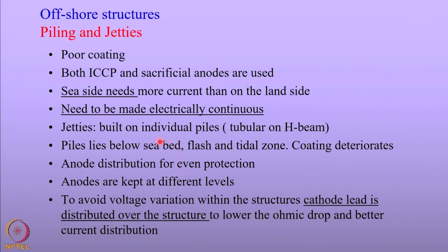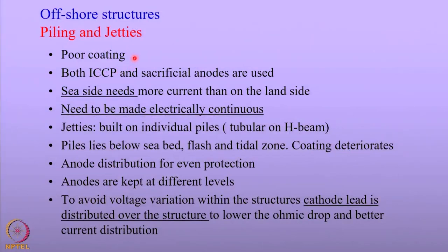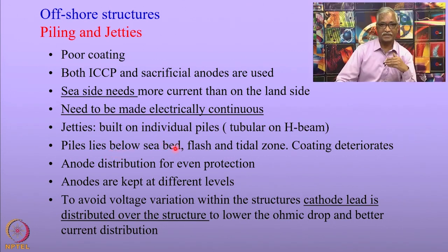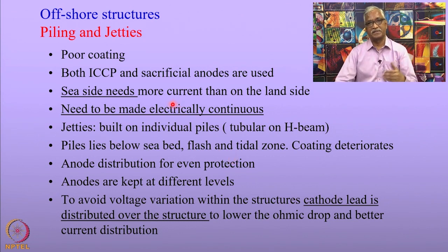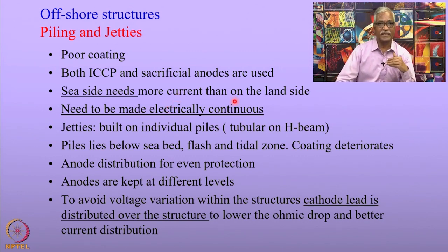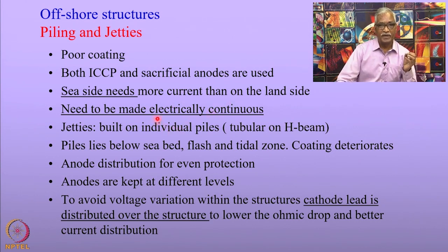Care needs to be taken to avoid stray current corrosion of structures. For piling and jetties, good coatings are essential — poor coatings are a cause of concern. One problem in piling and jetties is that in splash and tidal zones, the coating deteriorates because of continuous washing by seawater. If structures on the offshore and onshore sides are connected, the sea-side structure requires more current than the land-side structure and they need to be made electrically continuous.